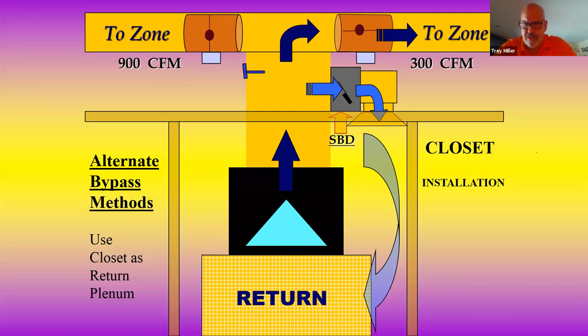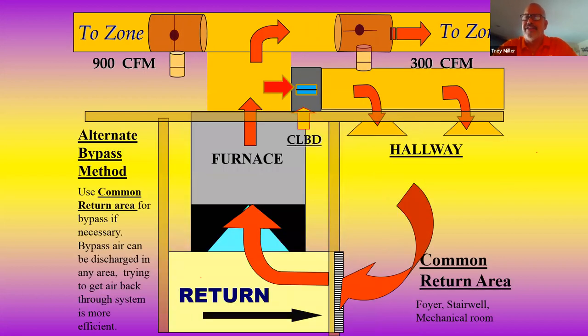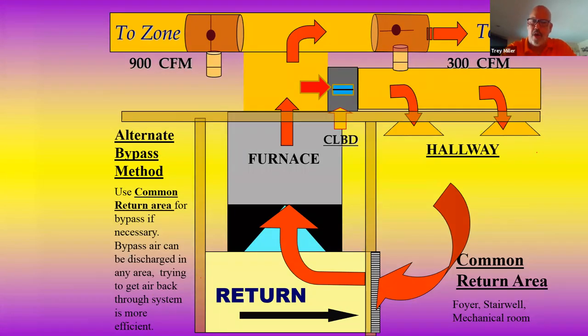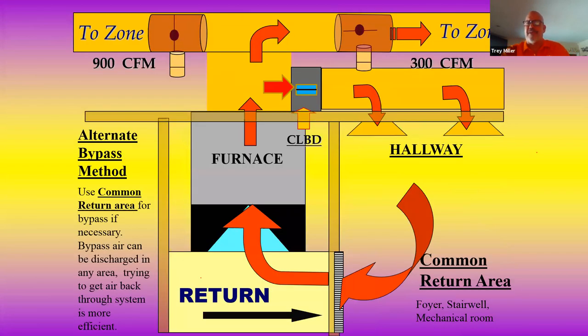But let's just say we have a gas furnace or we are not allowed, and we have no way to connect the supply to the return. What we can do is go to our hallway or go to an area and dump the bypass air into an area where we're pulling return. This makes things a lot easier. Guys, it makes it very nice as far as it.